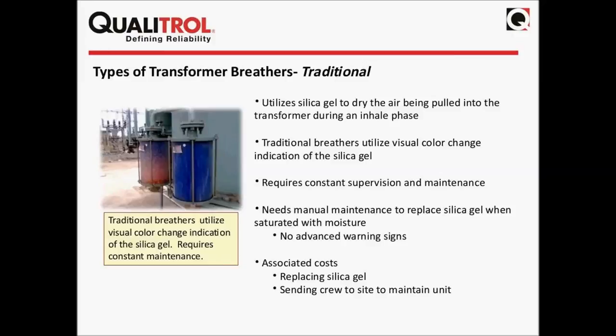So again, it's the cost of sending that crew out there, replacing the silica gel, and just the constant maintenance of somebody having to watch it and make sure that it's not saturated and it's not this blue color for a long period of time, because it cannot remove any additional water from the atmosphere.